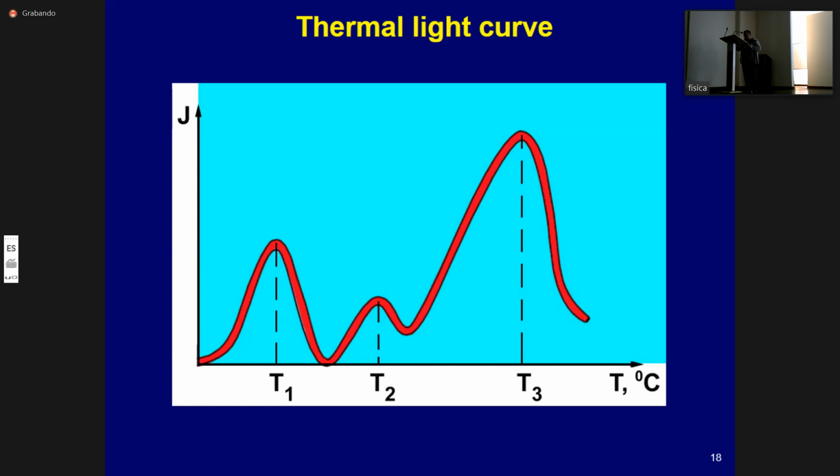However, with the integral method, it is necessary to take into account fading, the decrease of detector readings over time. Fading is due to the presence of low temperature peaks in the phosphor and the possibility of recombination of charged carriers even at room temperature.